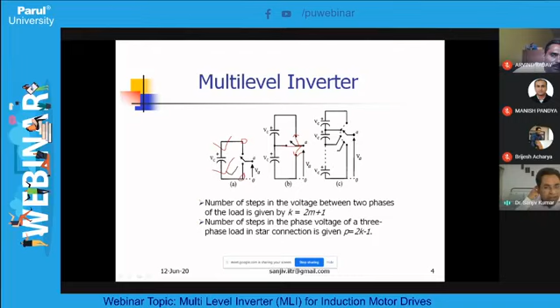The more the number of levels, the more the waveform goes towards the sinusoidal shape. The advantages of multi-level inverter operation are that it can generate output voltage with extremely low distortion and low dV by dt. As the number of stairs increases, the waveform, which in a two-level inverter just went from 0 to VDC or VDC to 0, now goes from 0 to VDC by N, then 2 VDC by N, then 3 VDC by N, then 4 VDC by N, and so on. So there are stairs, and it approaches the sinusoidal. It also has low dV by dt, because switching now happens in steps of VDC by N. This is the advantage of multi-level inverter operation.